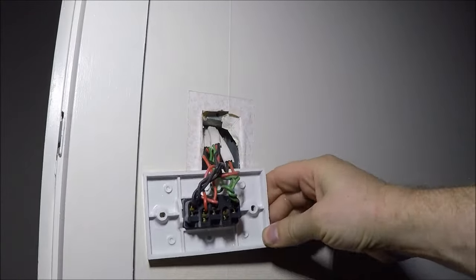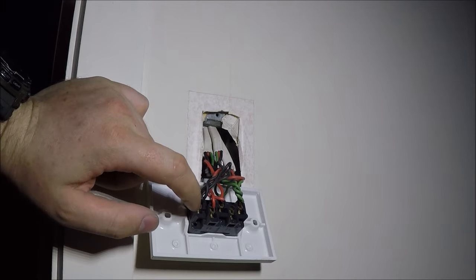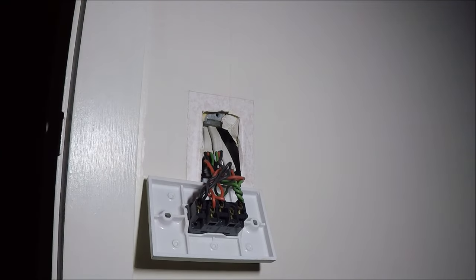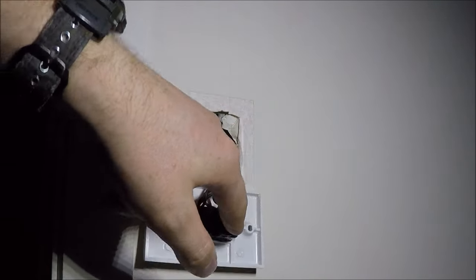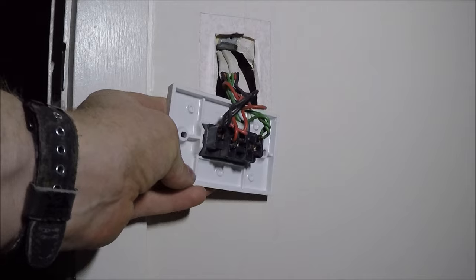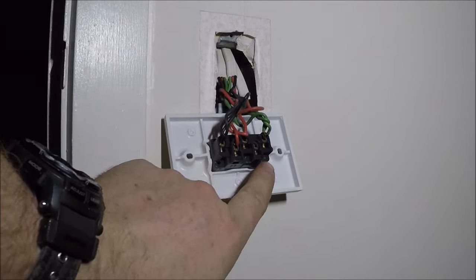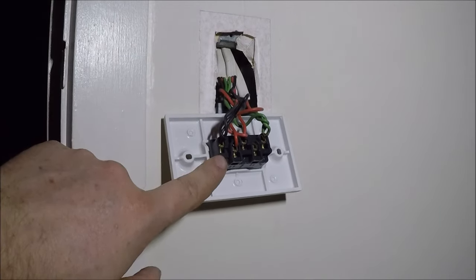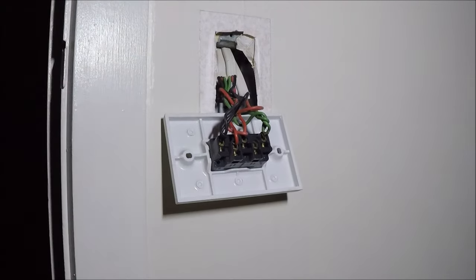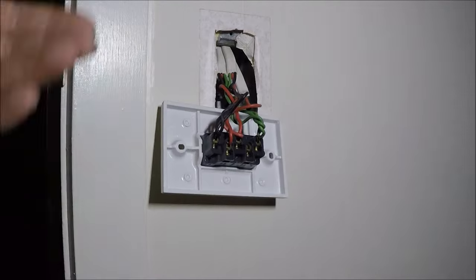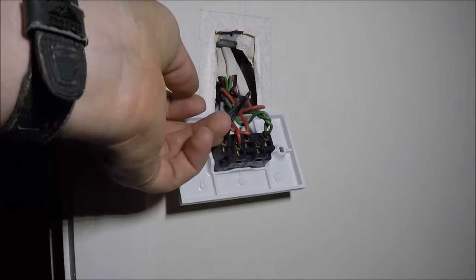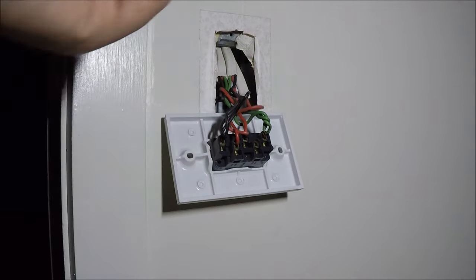Now as you can see on the back of this one, we've got our black cables twisted up and terminated in there, and our green cables the same. On this fitting here, the outside terminals are loop terminals, which means they're not actually part of this switch. They're a bit different to the new ones. So what I'll do is I'll take the blacks and the greens out and put them in separate connectors.